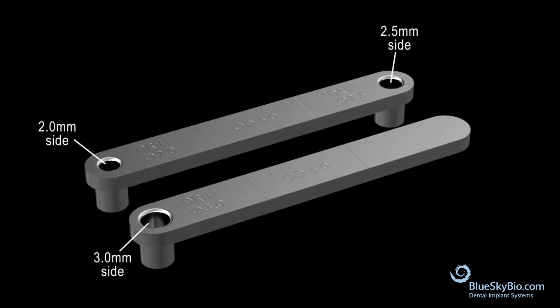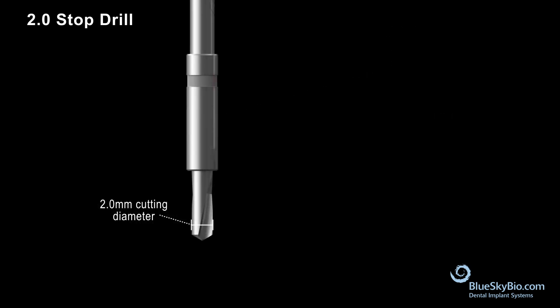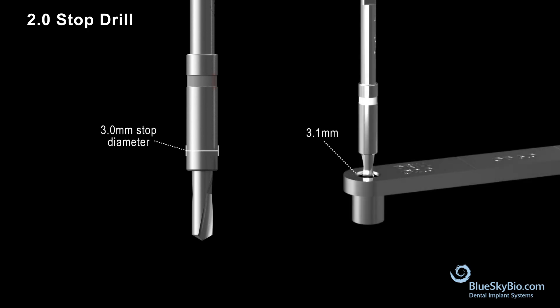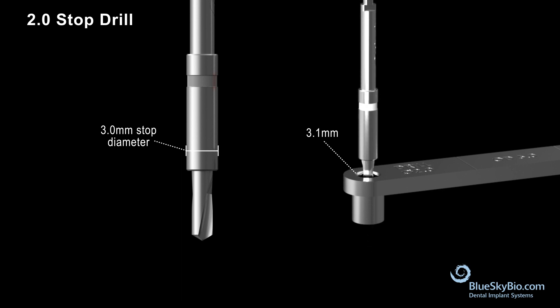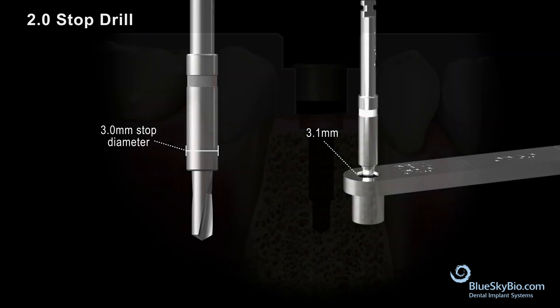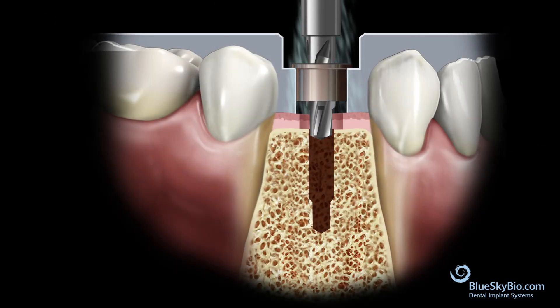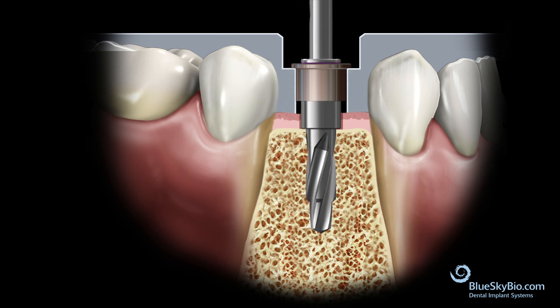The holes are marked by the diameter of the cutting aspect of the drill. The smaller diameter is the cutting diameter — in this case 2.0 millimeters. This is the stop diameter of the drill. The hole in the key is large enough to allow the stop section of the drill to pass. Each diameter drill has a specific stop diameter that matches a specific key. The guide tube will precisely guide the trajectory of the drill.